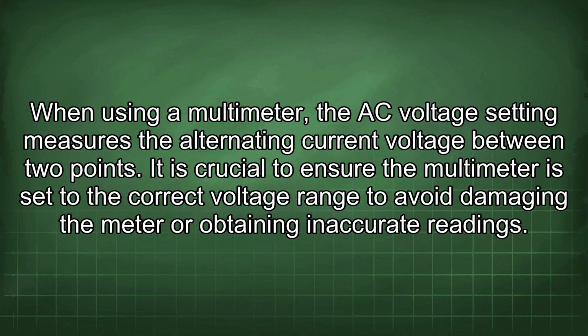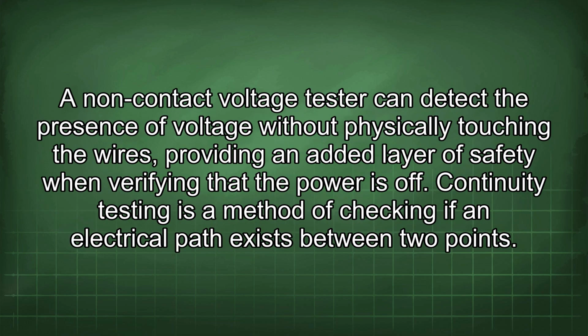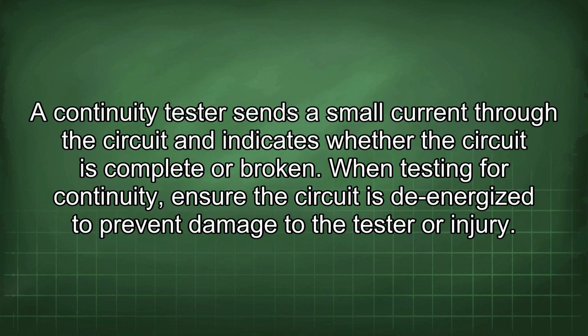When using a multimeter, the AC voltage setting measures the alternating current voltage between 2 points. It is crucial to ensure the multimeter is set to the correct voltage range to avoid damaging the meter or obtaining inaccurate readings. A non-contact voltage tester can detect the presence of voltage without physically touching the wires, providing an added layer of safety when verifying that the power is off. Continuity testing is a method of checking if an electrical path exists between 2 points. A continuity tester sends a small current through the circuit and indicates whether the circuit is complete or broken. When testing for continuity, ensure the circuit is de-energized to prevent damage to the tester or injury.